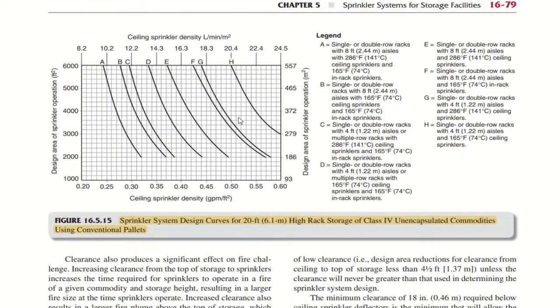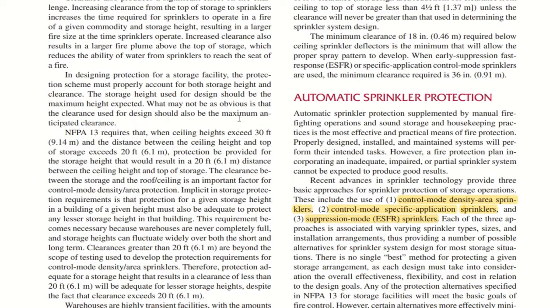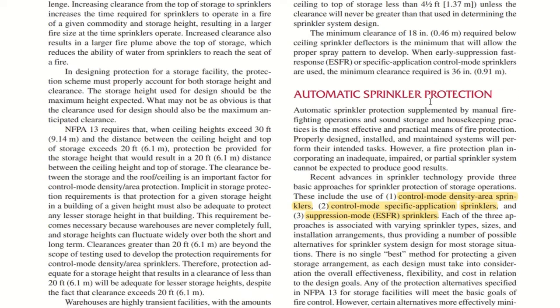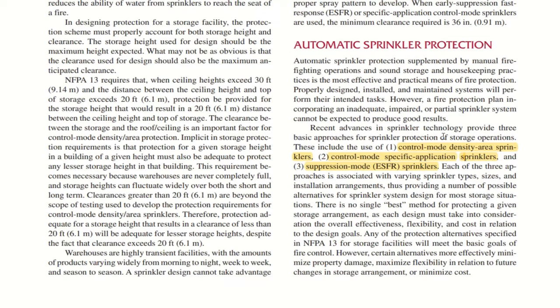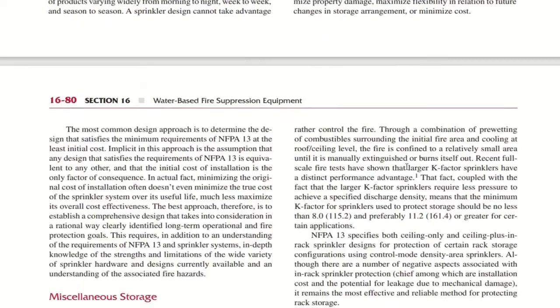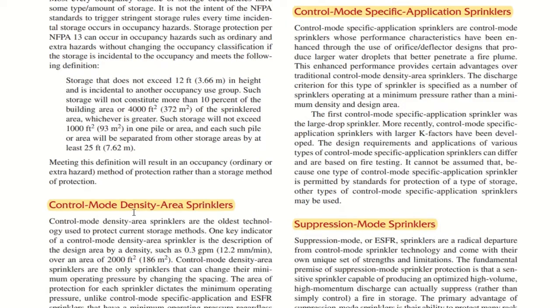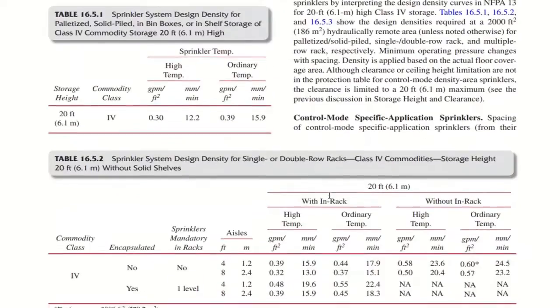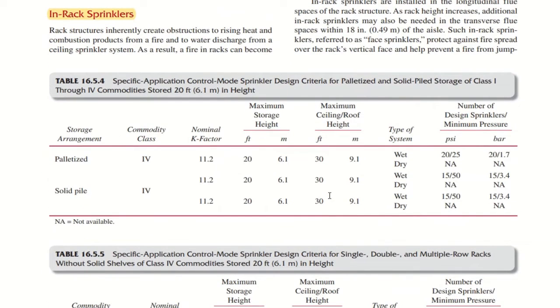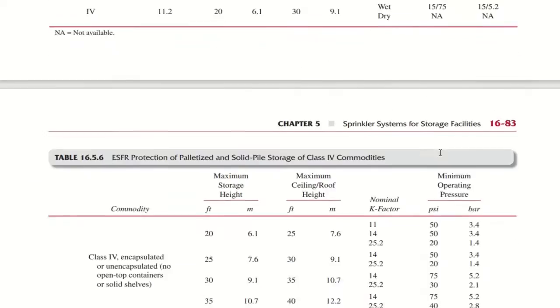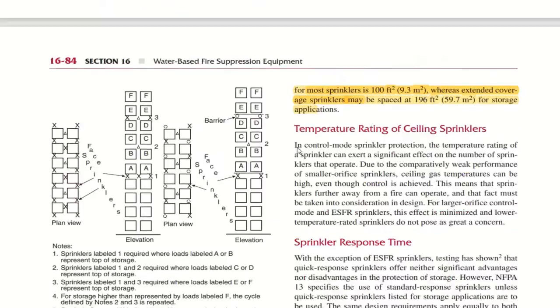There is some graph. This we are also covering in our NFPA 13 series. You can go through that. Here you have various approaches for sprinkler protection of storage applications. These include the use of control mode density area sprinklers, control mode specific application sprinklers, and early suppression fast response sprinklers. So you have various data related to these in these slides. For in-rack sprinklers, maximum storage height and ceiling height, based on that, the number of sprinklers to be considered is mentioned here. You just go through these things.